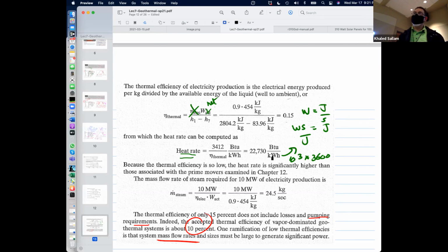You got me? Okay, so because of this I also ask a lot in the exam about the heat rate, and you shouldn't really panic. All you do is calculate the efficiency, like we always do in all the cycles, and the heat rate is 3,412 divided by the efficiency, whether it's 40%, 30%, whatever your eta is. That will give you the heat rate in BTU per kilowatt hour. That's the only thing you need to remember: heat rate equals 3,412 over eta thermal.